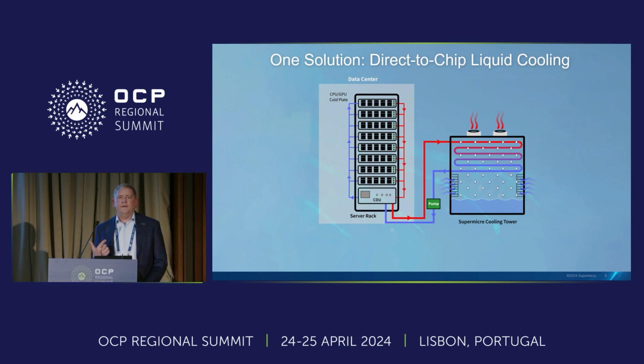That will have a facility water loop, a different loop, going out to a cooling tower or a liquid-to-liquid heat transfer mechanism. In this case, we've shown an air-based liquid cooling tower, which through evaporative cooling and other processes will cool that hot water back down 10 to 20 degrees Celsius so it can loop back into the racks, creating a continuous cycle.